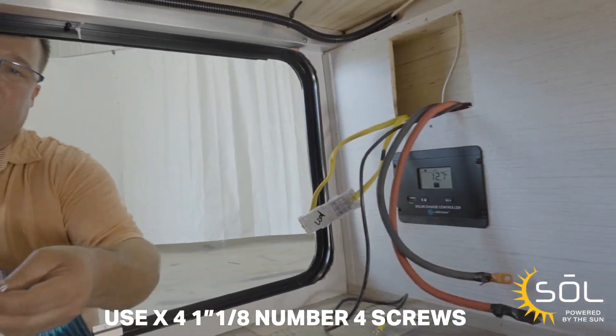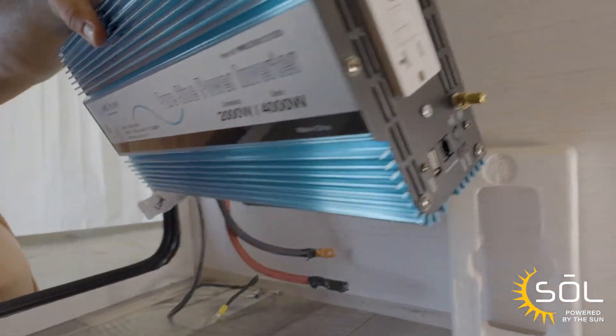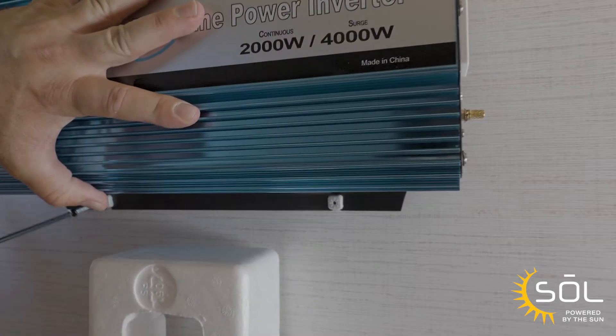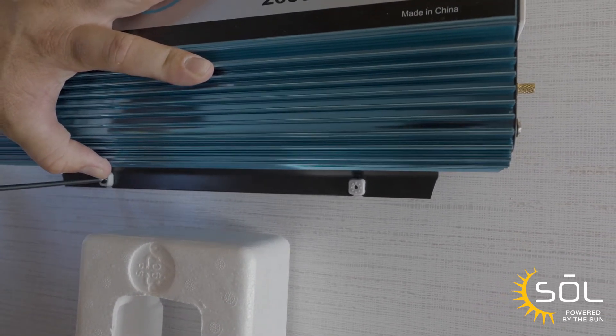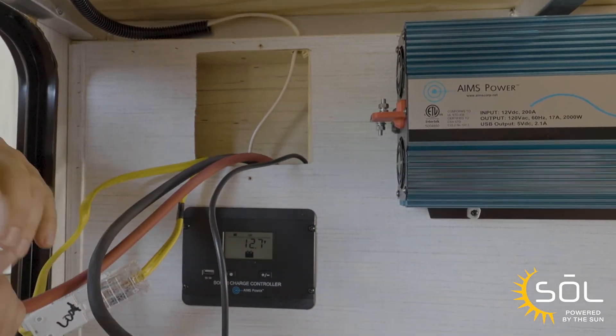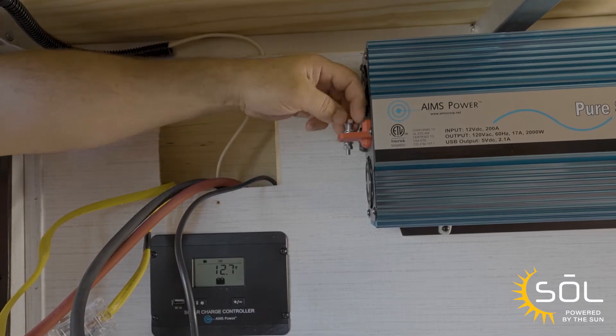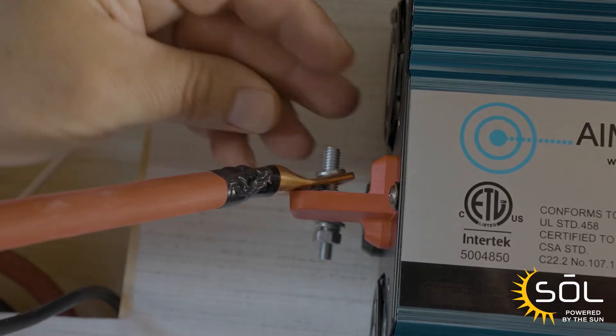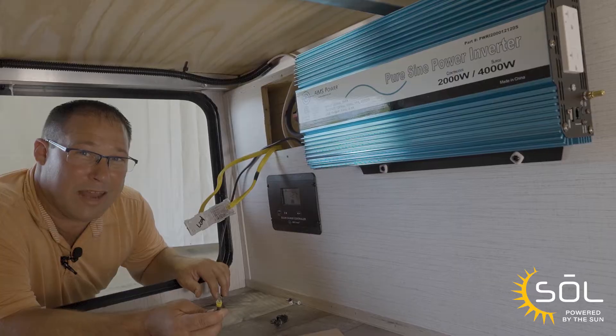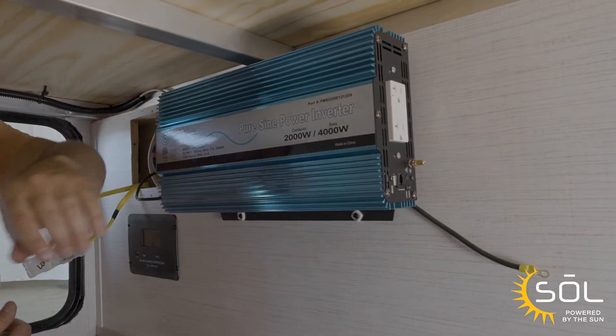We're going to use four number-four, inch-and-an-eighth screws to mount the inverter. Next we're going to connect the battery cables to the inverter — connecting the red cable to the positive side of the inverter. Now that we've got the positive connected, we're going to connect the negative side following the same process. Next, we're going to attach the chassis ground by feeding it through the backside and attaching it to the brass screw.